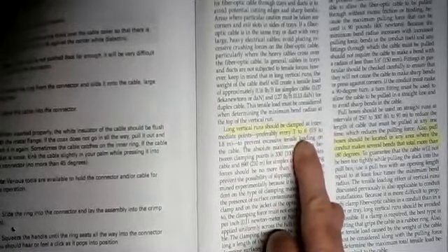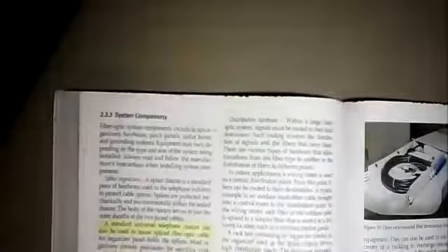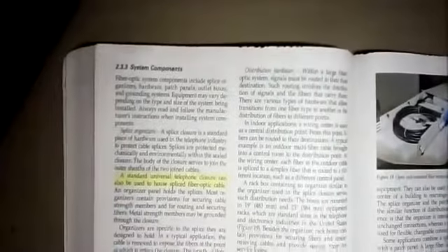to 6 feet. This is installation in cable tray and ducts. You need to clamp it every 3 to 6 feet. And on the right-hand column, it says also pull boxes should be located in any area where the conduit makes several bends that total more than 180 degrees. With electrical conduit, we're restricted to 360 degrees, but for telecommunications, they cut that in half. They say 180 degrees. If you have more than 180 degrees in a line, then you need to have a box.